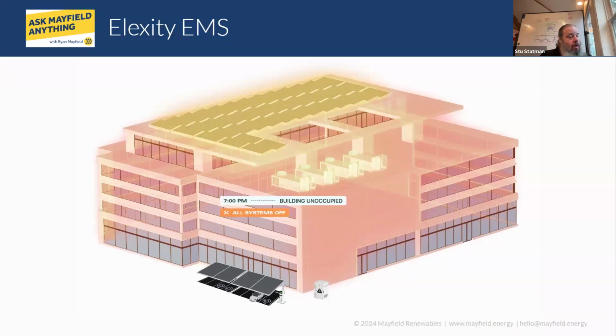The EV chargers are typically Modbus TCP locally, although for ChargePoint we can reach out to the ChargePoint cloud. For the thermostats we'll be using specifically, they create their own wireless mesh network, and then there's a gateway that we communicate to, in this case going back out to the cloud, although we could also go directly to them using BACnet, which is an old school building communications technology.